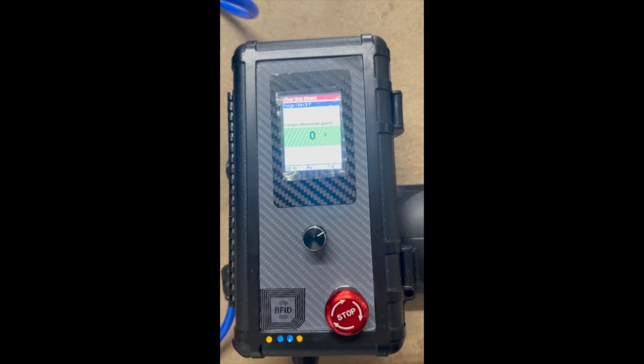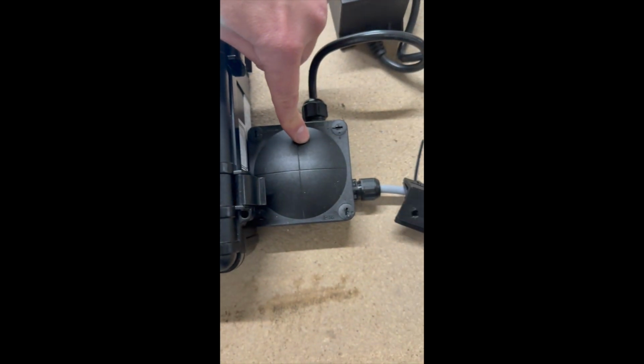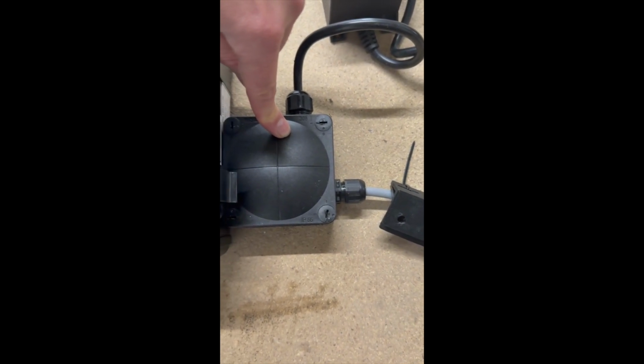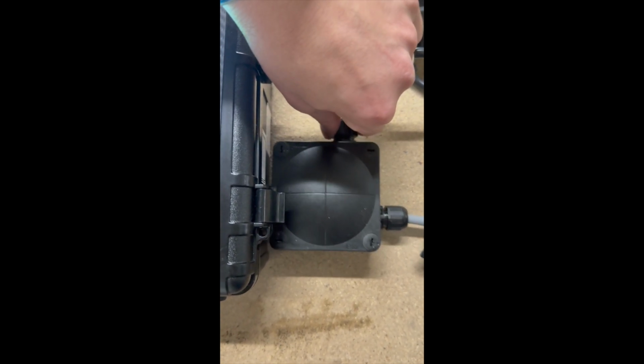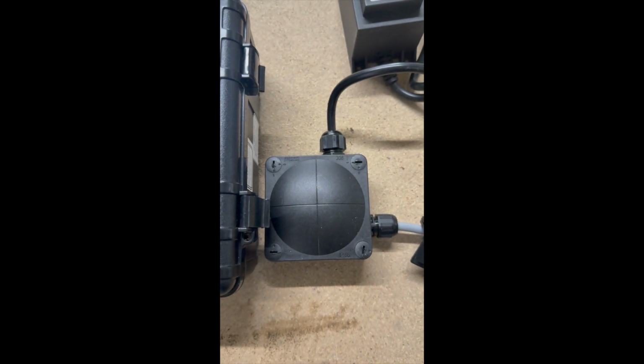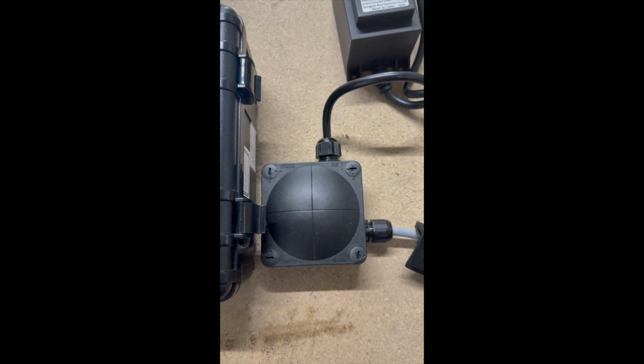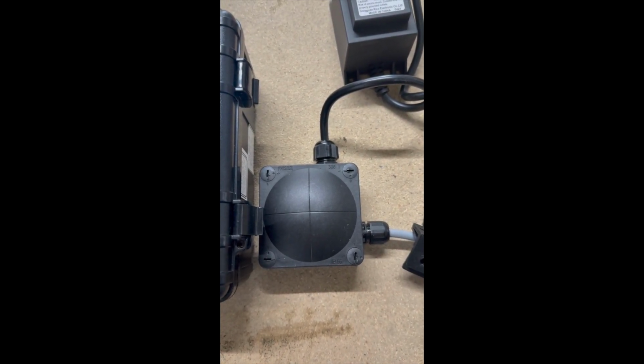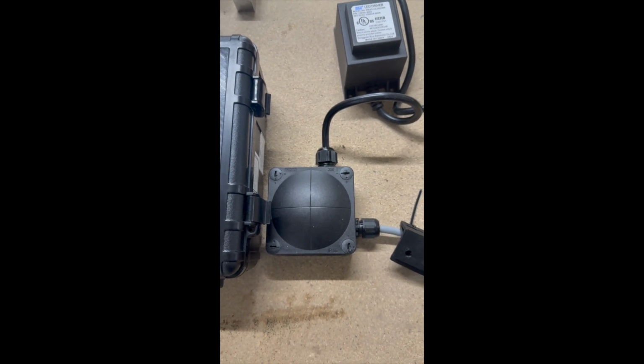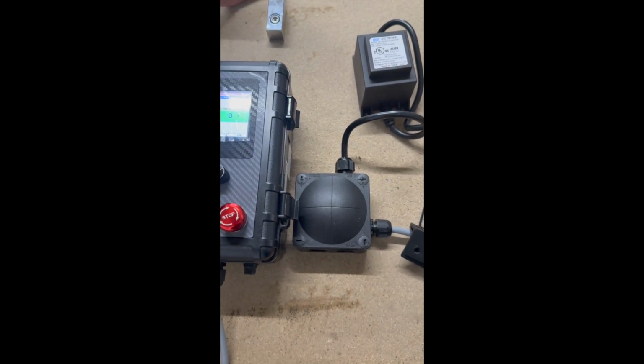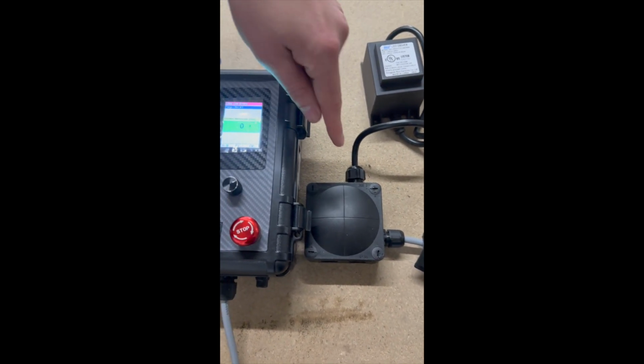If carbon monoxide is found, this will turn to red, and using this device you can also turn the compressor off. We have stop connectors in this control box, connection box, that you can wire to the emergency shut off switch of the compressor. That way, if the CO is detected, this unit will turn the compressor off.